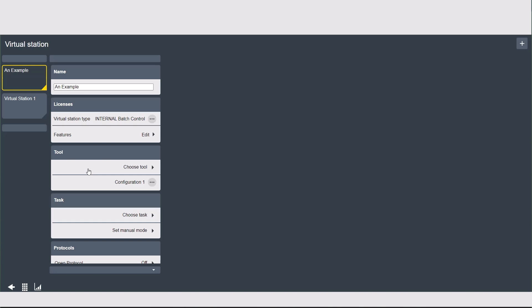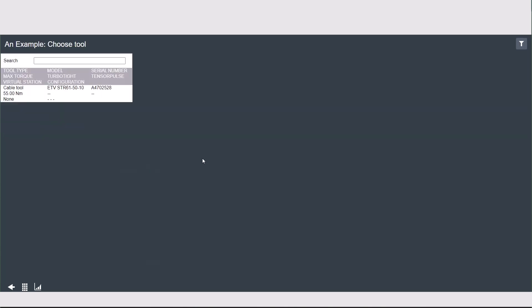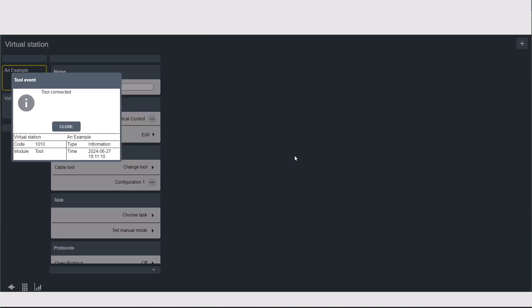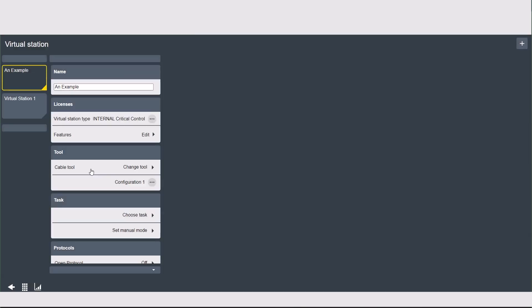The tool tab is where you're going to assign a tool to a virtual station. When you want to assign a tool, you're going to click 'Choose Tool' and the list of all the tools currently paired to the controller will show here. If a tool is already assigned to a virtual station, it's going to appear gray, and available tools are going to show in black text. To help you find the correct tool in the list, it's going to give you some basic information such as the max torque of the tool. Once a tool is paired to the virtual station, you're going to see a pop-up that tells you it's connected to the controller.